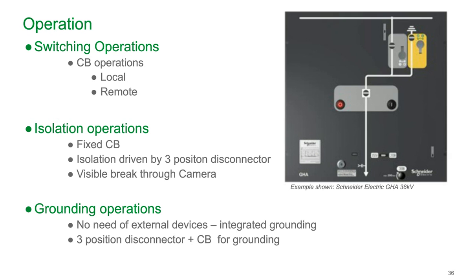The active mimic bus indicates the open or close, but also gas-insulated switchgear typically has a visible break. So as an IEEE requirement, you either have a window or a camera. On Schneider products in particular, they typically have a camera that's viewable, either plug in via USB through the front to a laptop, or viewable through an HMI on the front of the switchgear. That's the most common option, but there's also windows on some other products to show the visible break.